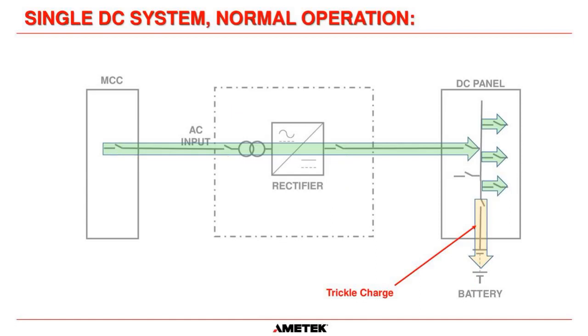Okay. So the normal power flow, if you follow the green arrow, is your 480 will go into the rectifier. That gets converted into DC. The DC goes to the DC panel. And the only reason that the charger feeds the load circuits, and this is for, let's say, for example, for a 60 cell system, our voltage here is going to be 135 volts.